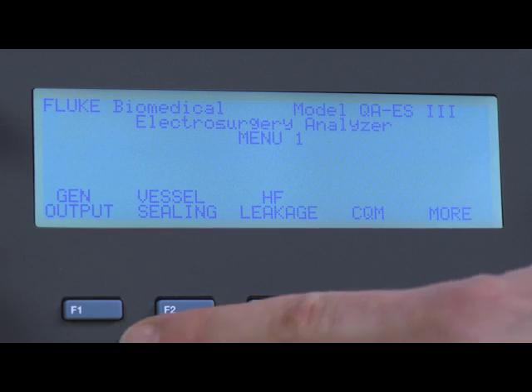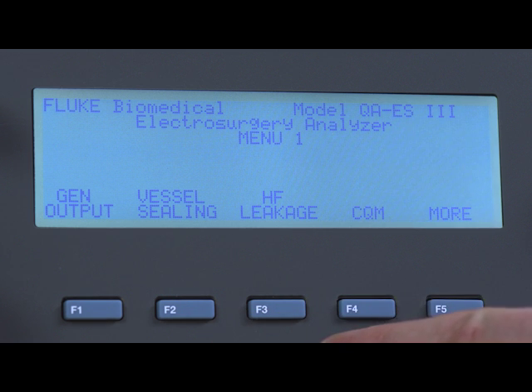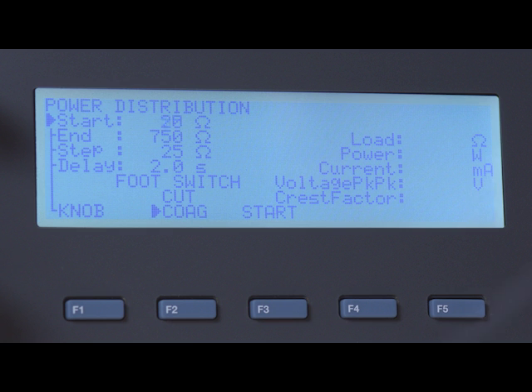The QA-ES III collects all measurements including vessel sealing, high-frequency HF leakage, contact quality monitor, and output power distribution in single or continuous mode. It also measures cut and coag waveforms with either monopolar or bipolar outputs.